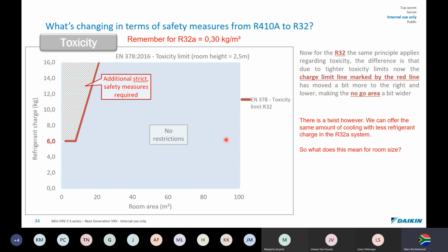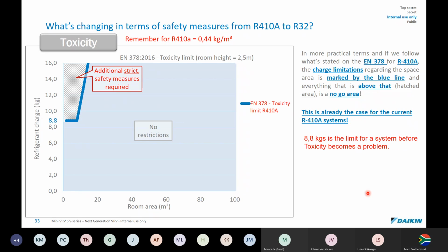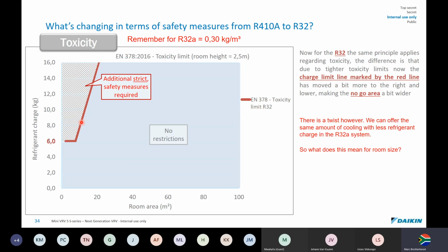So if this system was designed on, say, a 6 horsepower system, I would need 8.8 kilograms. If I put a 6 horsepower system of R32, I'd drop it down to 6, but because R32 is more energy efficient, I might not need a 6 horsepower system. I can use a 5 horsepower system, which will use less refrigerant in it than a 410 system.